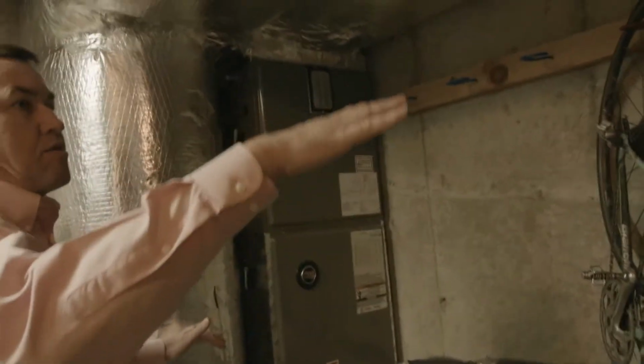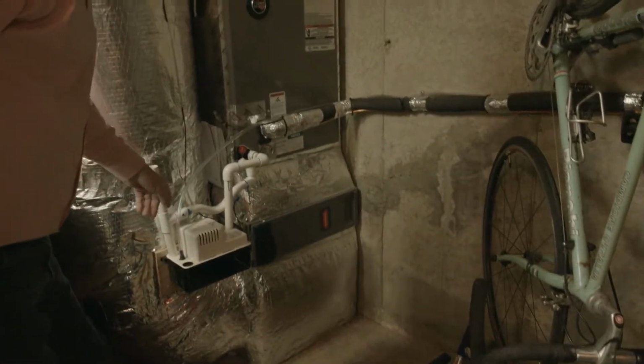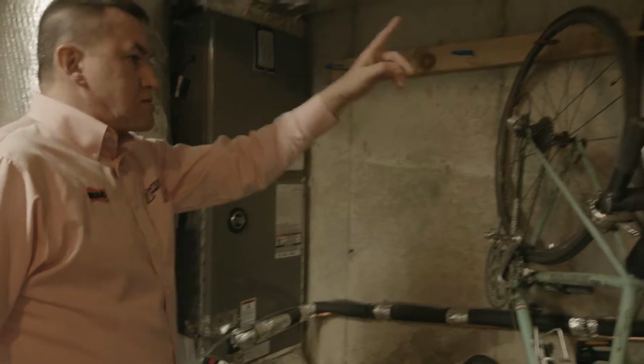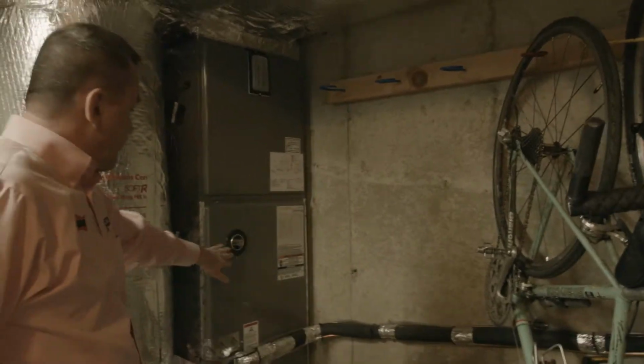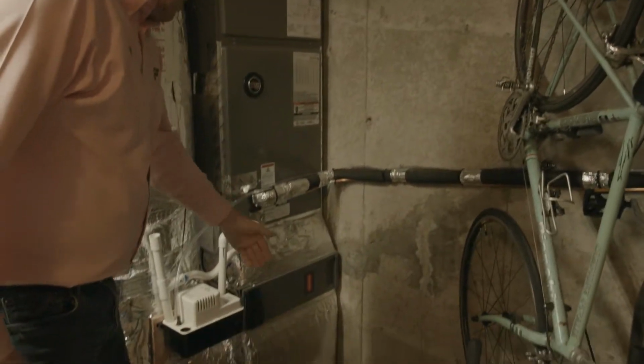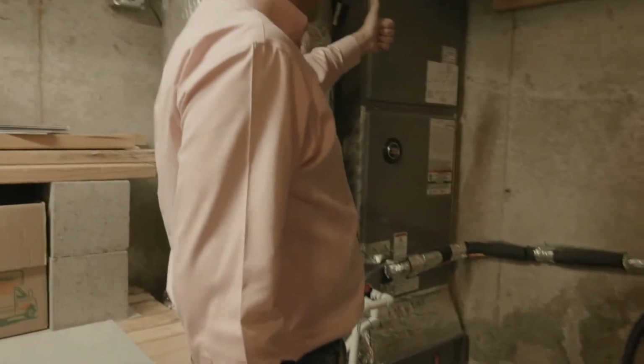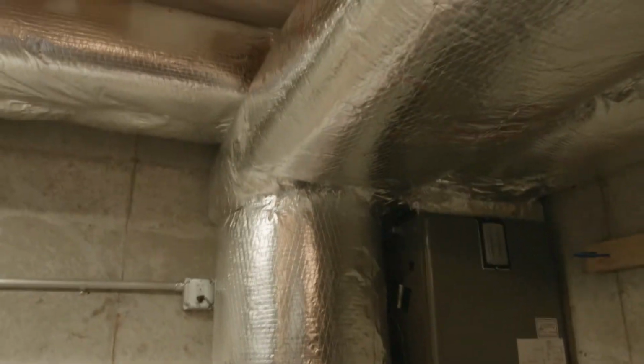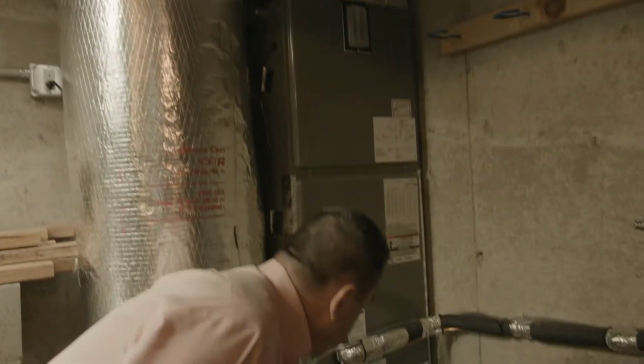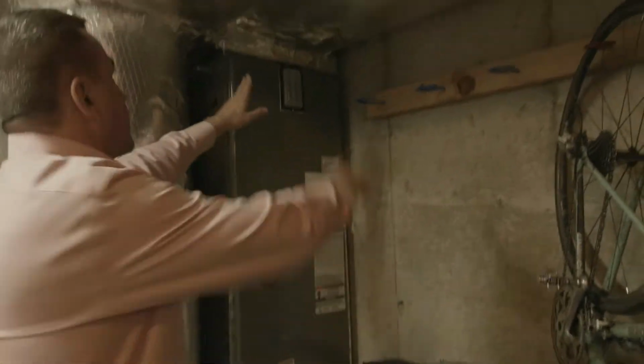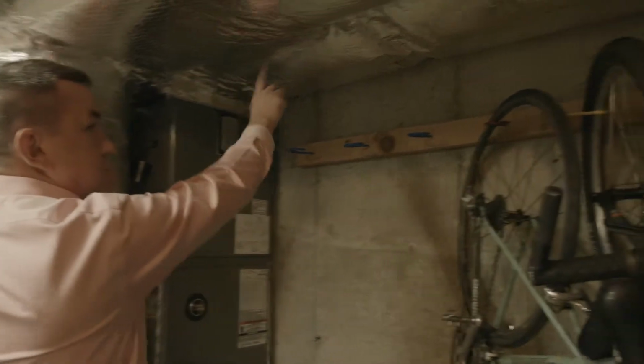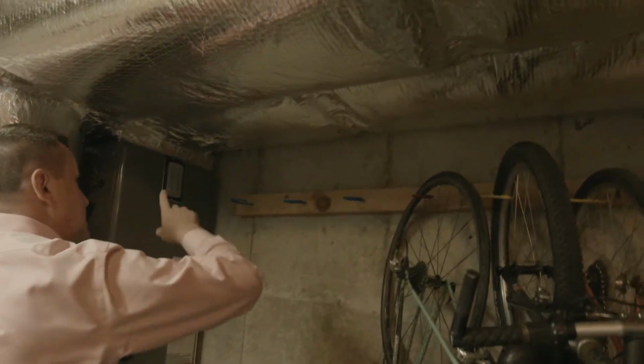We're actually below ground level here, so we have a condensate pump that will pump the condensate outside in air conditioning mode from the coil. It's an upflow configuration, so return air is coming back through the filter, clean air goes to the air handler and then goes through the supplies, two different supplies.